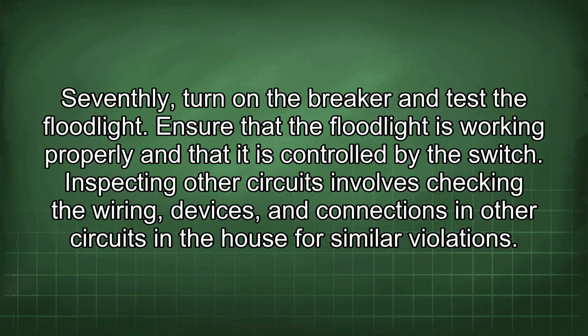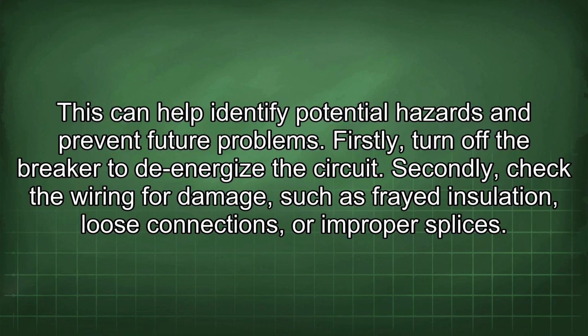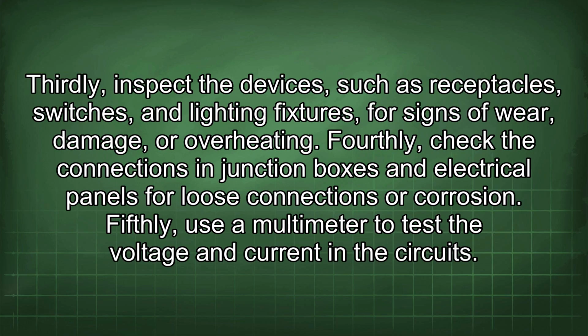Inspecting other circuits involves checking the wiring, devices, and connections in other circuits in the house for similar violations. This can help identify potential hazards and prevent future problems. Firstly, turn off the breaker to de-energize the circuit. Secondly, check the wiring for damage such as frayed insulation, loose connections, or improper splices. Thirdly, inspect the devices such as receptacles, switches, and lighting fixtures for signs of wear, damage, or overheating.